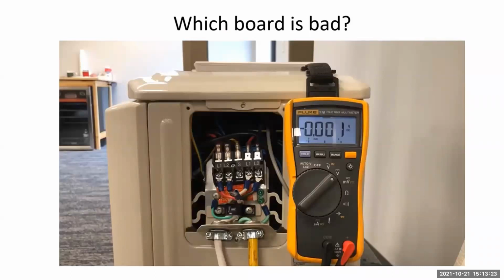And now we're going to check out which board is bad. Now there's a couple ways to check this. This is the first way I like to check it, and then I'll go into the second way later. So with the S wire connected indoors and the S wire disconnected from the outdoors, you apply power, you position your red lead and your black. The positioning of your red lead and black leads is very crucial.